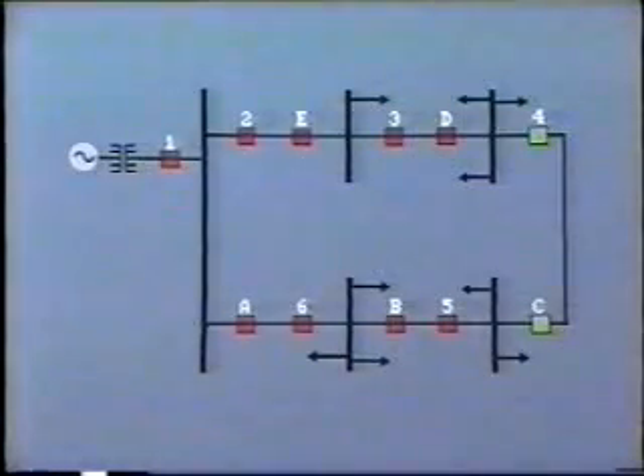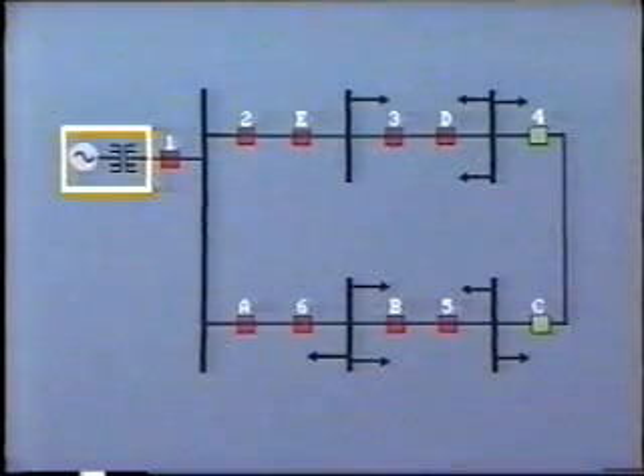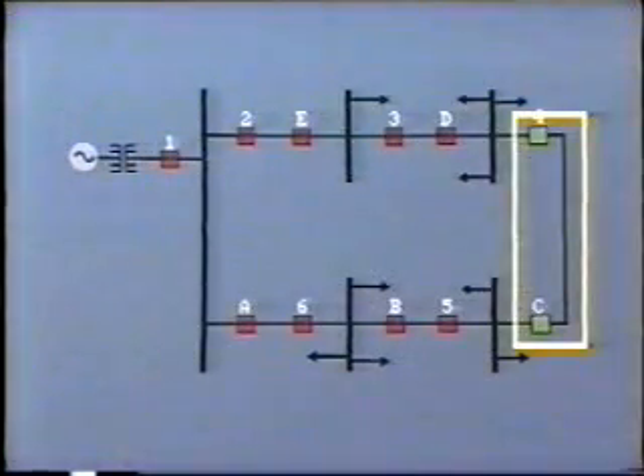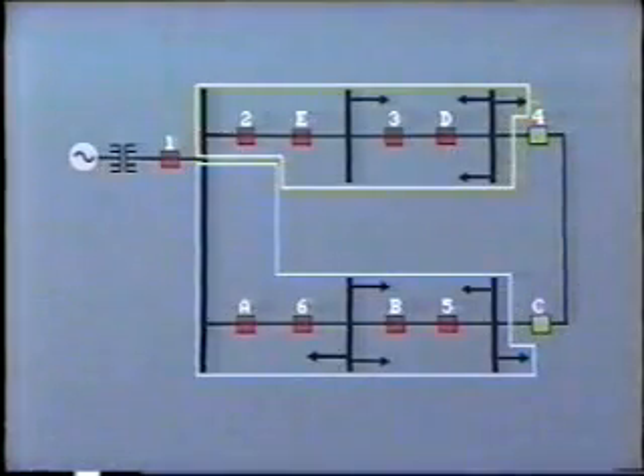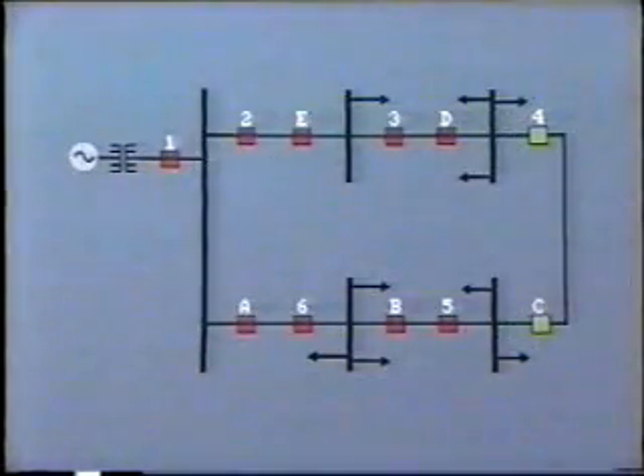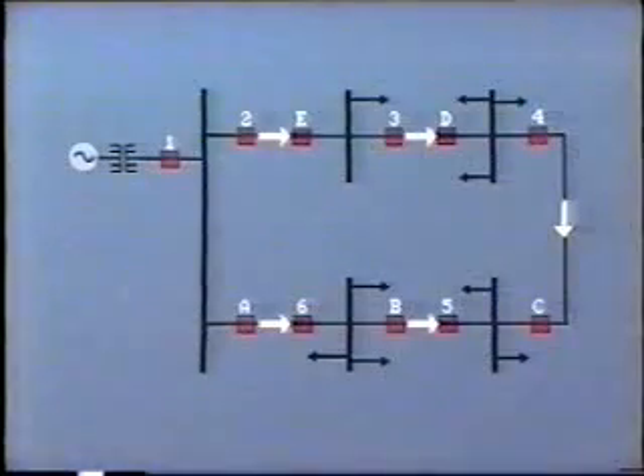As we mentioned before, a loop arrangement is generally employed in sub-transmission systems and even in the distribution system on occasion. In its simplest form, there is only one source of supply, and the loop is often split, usually at the far end. In this case, we have effectively two separate radial circuits, and the protection coordination will be similar to that which we have just looked at in the previous segment. However, in order to provide increased reliability, the loop may be operated fully connected so that current flows in either direction around the loop, depending upon the magnitude of the load at different locations.